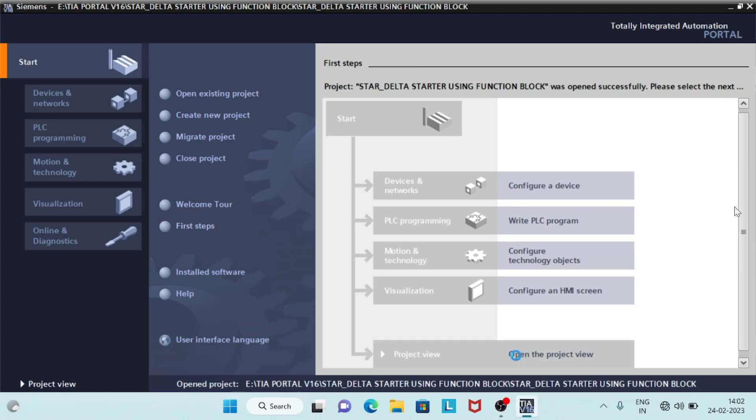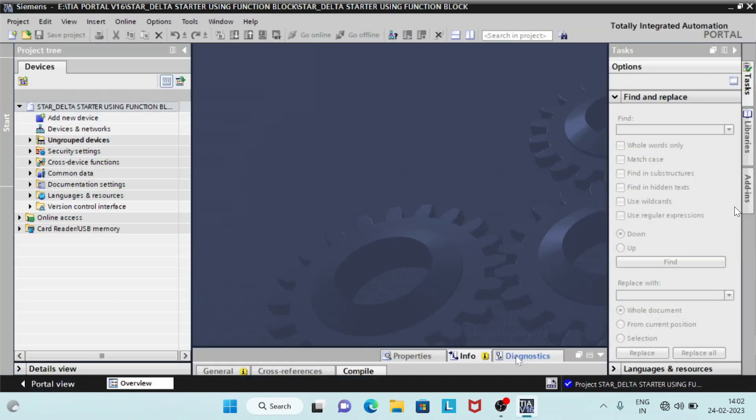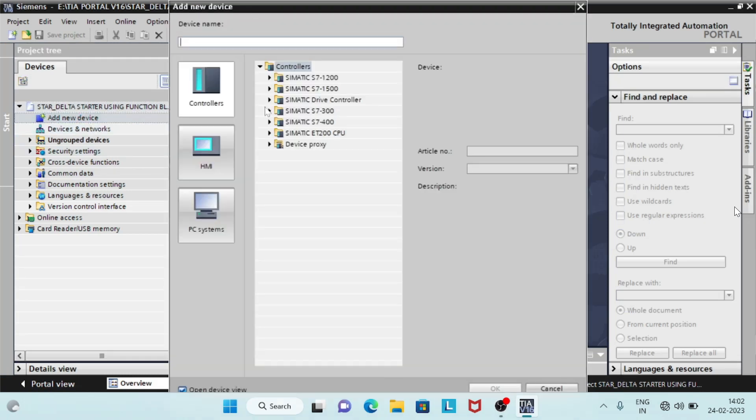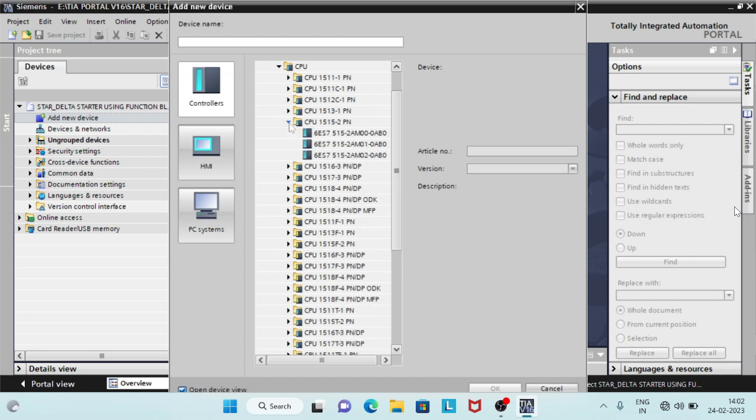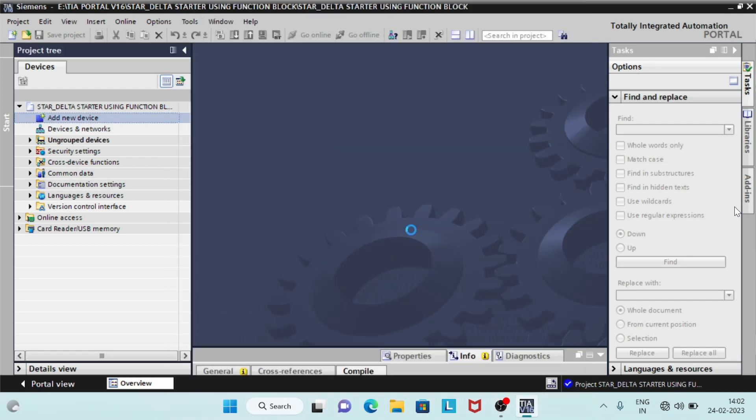Function blocks are code blocks that store their inputs, outputs and in-out parameters permanently in instance data blocks, so that they remain available even after the block has been executed. Function blocks can be called several times at different points in a program. Function blocks simplify programming of frequently recurring functions.